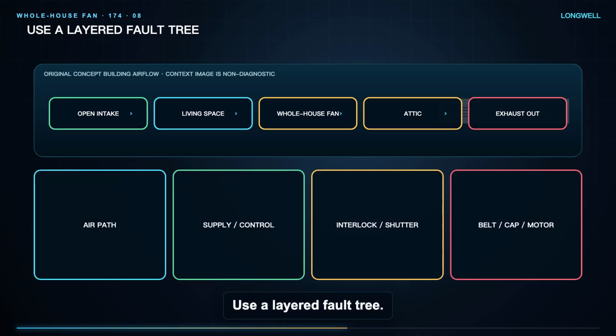Use a layered fault tree. First verify building air paths and the exact operating command. Then a qualified technician verifies supply and control output, safety devices and interlocks, shutter freedom, belt and wheel condition, capacitor where fitted, motor condition, and obstruction or overload. Each result determines the next test.